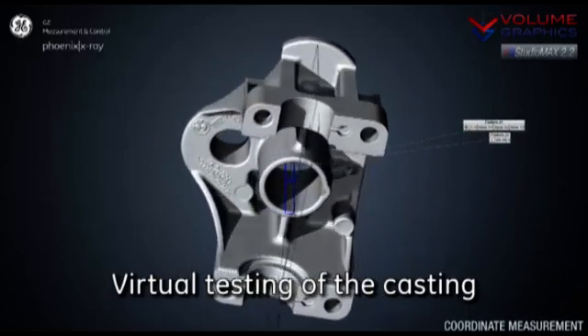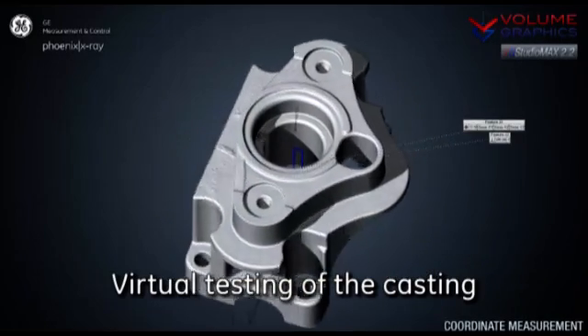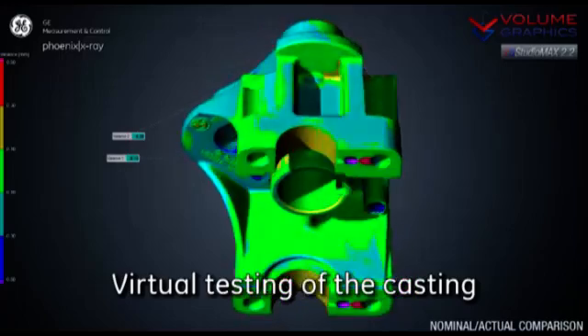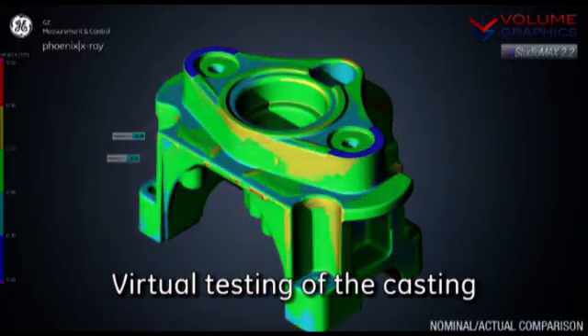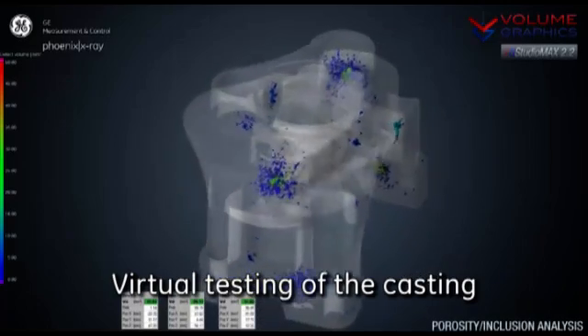In the analysis software you can see a virtual representation of the part — this is exactly this part type. We can immediately perform dimensional measurements in this virtual part; here you see typical dimensions taken as specified in the drawing. We can also place the three-dimensional CAD model on top of the part and do a direct comparison of the real part, the 3D model of the part, and the CAD model, to see where it deviates. We can also measure three-dimensional wall thickness of the part — all in one dataset with one package.